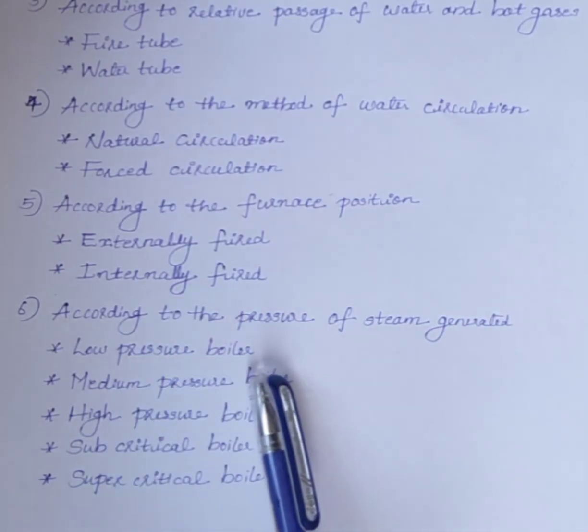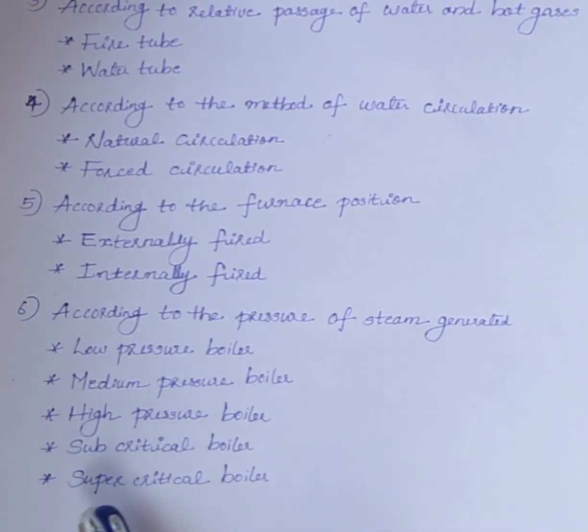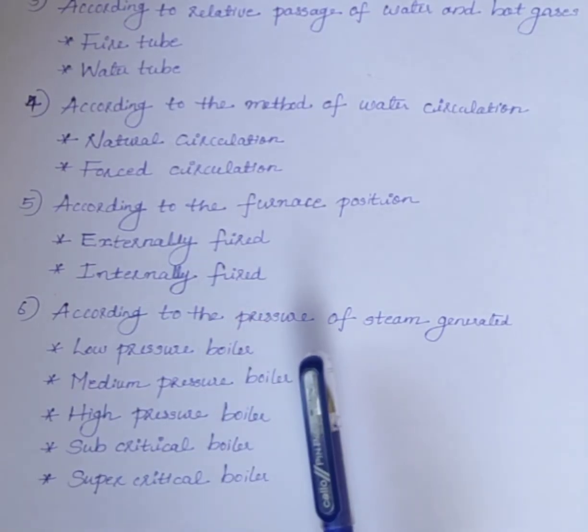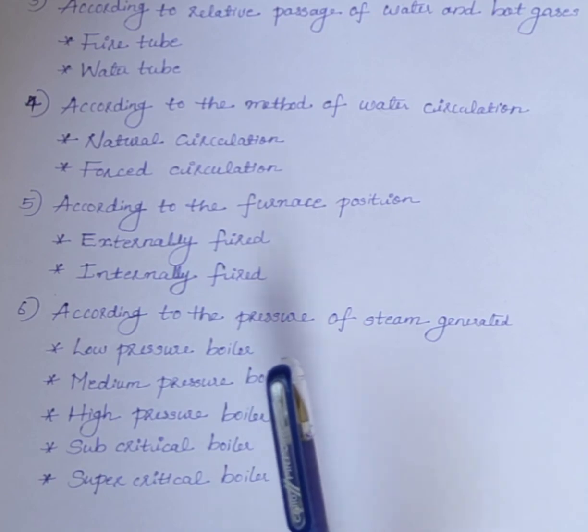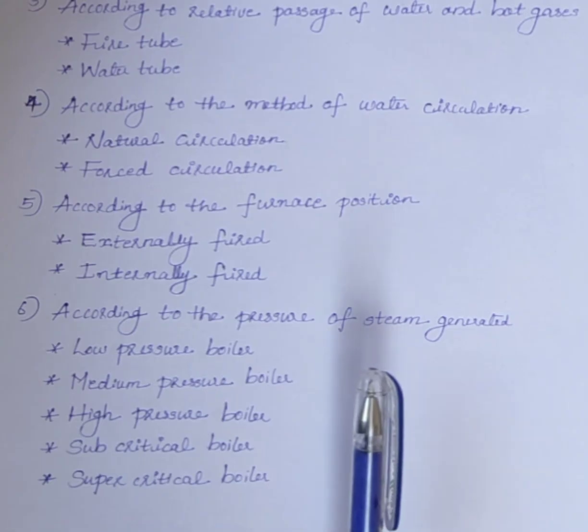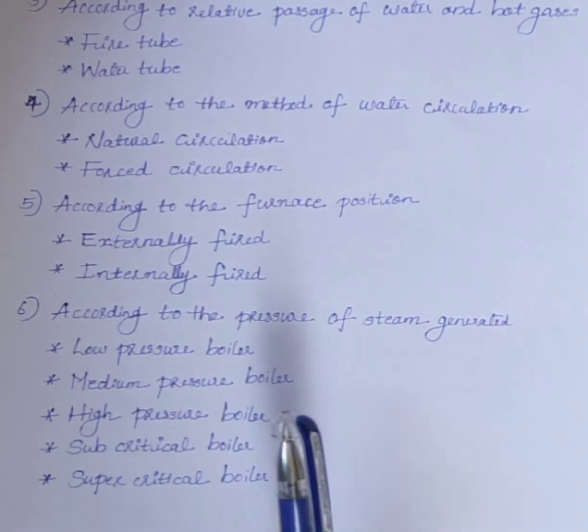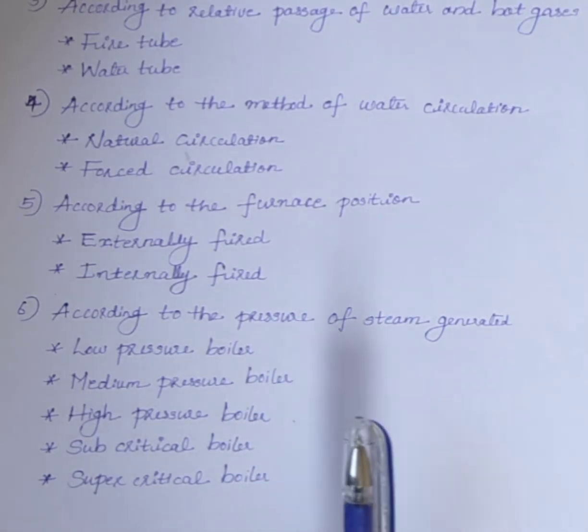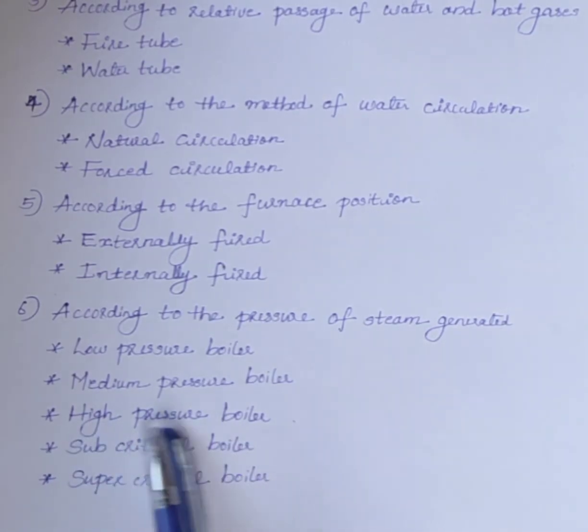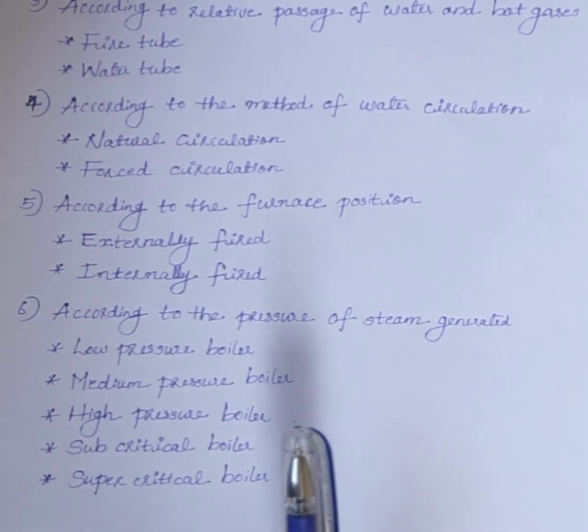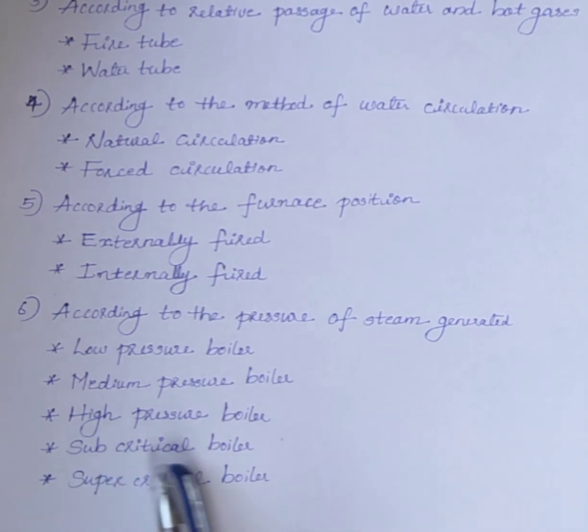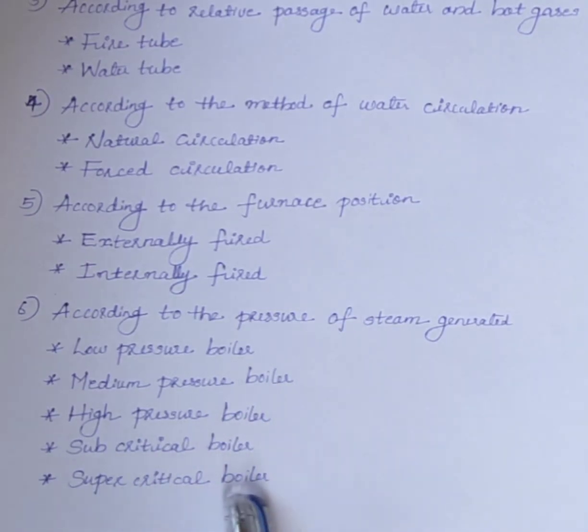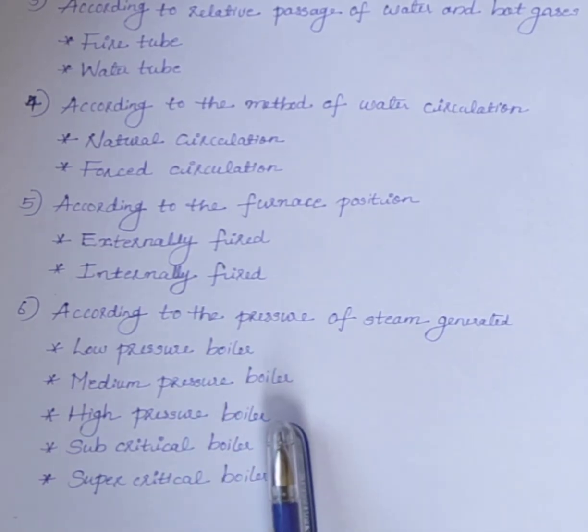The next classification is according to the pressure of the steam generated. Boilers are classified into low pressure, medium pressure, high pressure, subcritical, and supercritical boilers. A low pressure boiler produces steam at 15 to 20 bar and is used for process heating. Medium pressure boilers operate from 20 to 80 bars and are used for power generation or combined power and process heating. High pressure boilers produce steam above 80 bars. Subcritical boilers produce steam below the critical pressure, while supercritical boilers produce steam above the critical pressure.